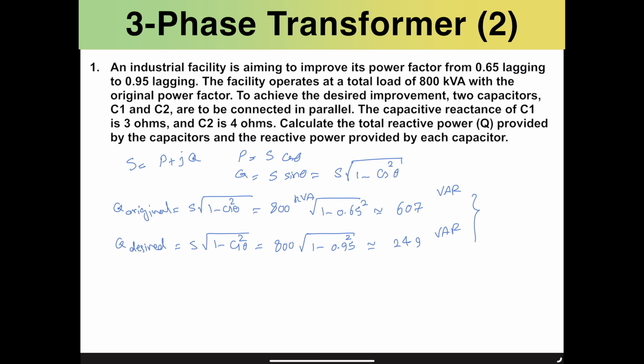The delta between them, delta Q, is around 358 VAR. This is the amount of improvement we expect to achieve by employing the two parallel capacitors C1 and C2 — this is the total reactive power provided by the capacitors, and it's a negative value in general that reduces Q.